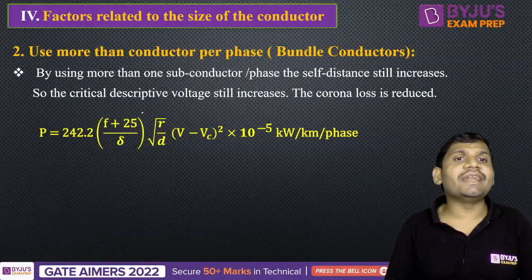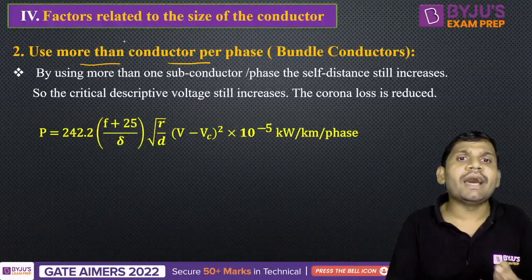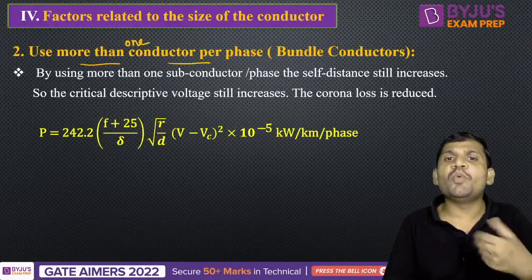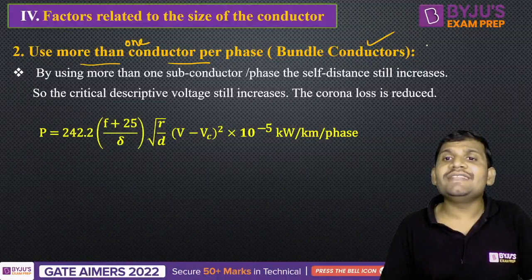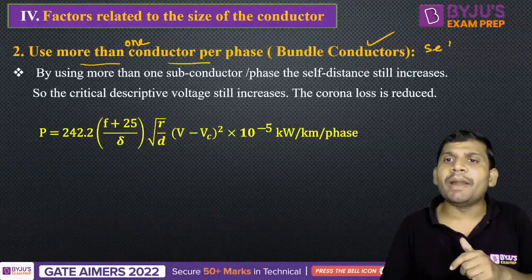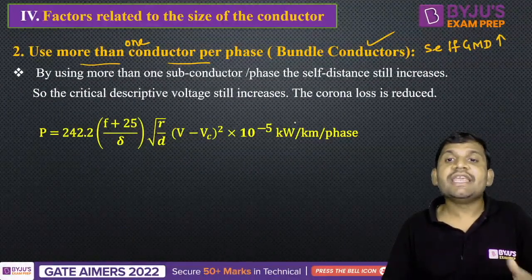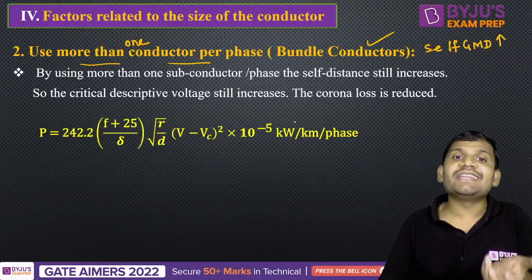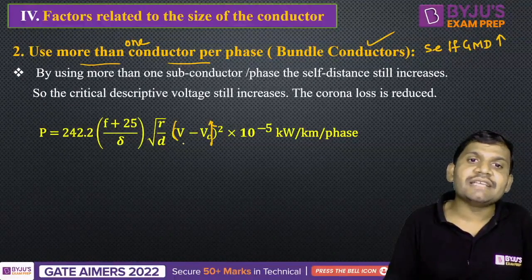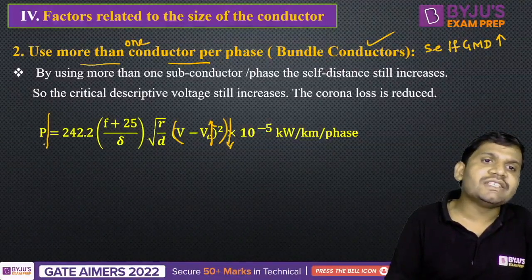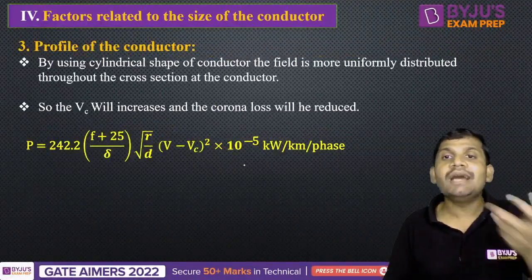One more factor related to size: use more than one conductor per phase, that is called bundle conductors. By using bundle conductors, the self-GMD (GMR) increases. If the GMR increases, then the critical disruptive voltage increases. When Vc increases, V minus Vc reduces, then power loss reduces. That is the reason why by using bundle conductors, we can reduce the corona loss.